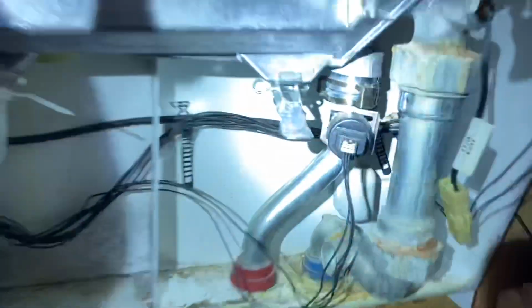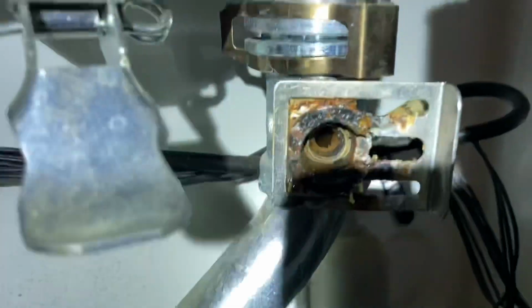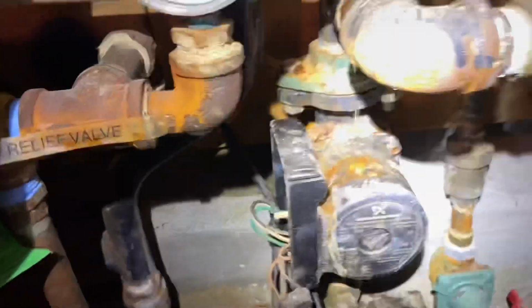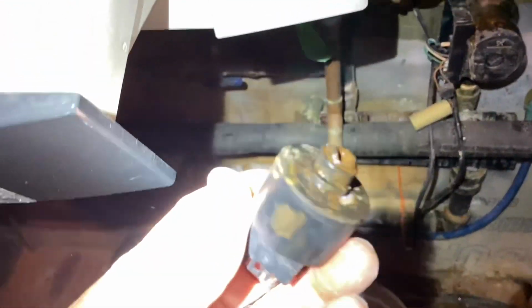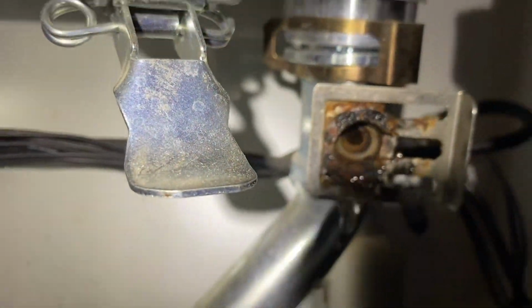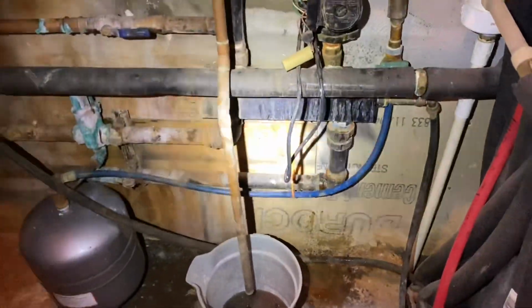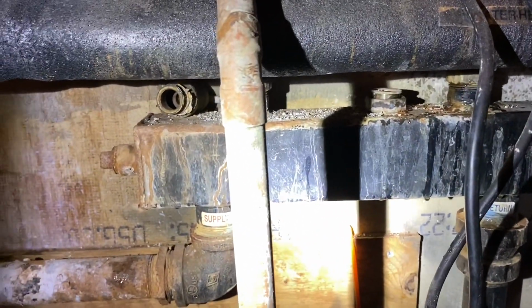Lack of communication. All right, so I took the pressure sensor out and closed the primary loop valves on the return and supply side. And look at that - filled with sludge. There hasn't been good maintenance here in a while, and they really need a magnet on the return side. Pretty bad actually, and all this black piping here and the hydraulic manifold, the separator right there.